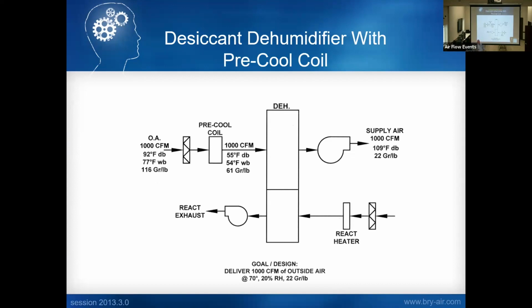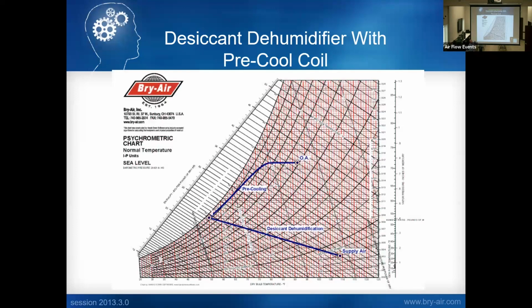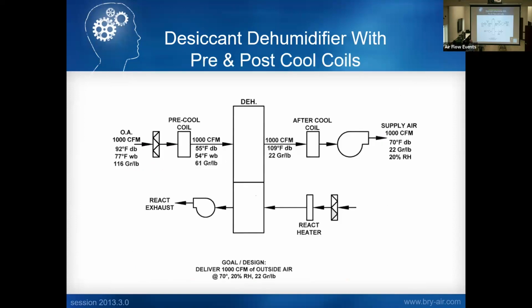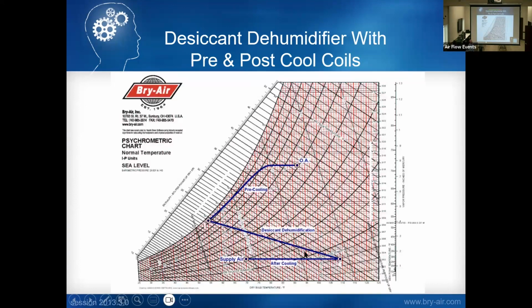But I still have that high outlet temperature that I need to deal with. You see that on the psych chart. So in those particular cases, we add a post-cool coil, which will take my 109 leaving the desiccant rotor and drop it down to whatever the customer needs, in this case, 70-degree supply air. And again, that after-cool coil would be chilled water or DX. Let me see that on the psych chart.